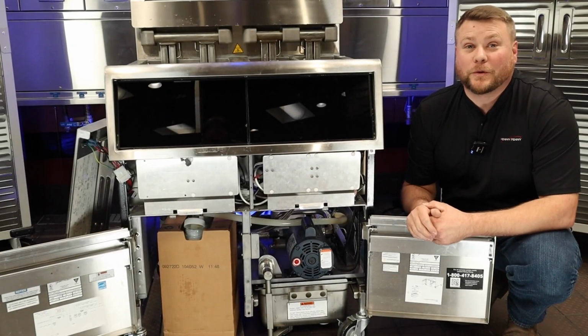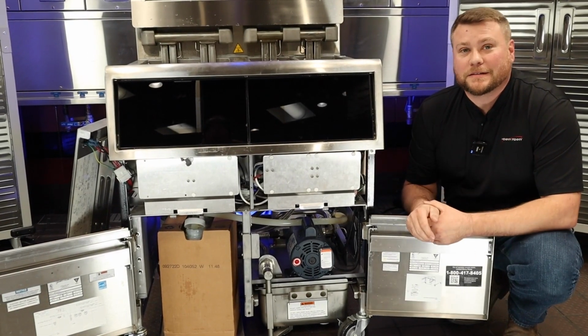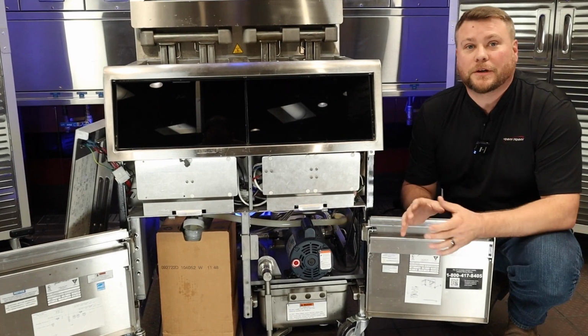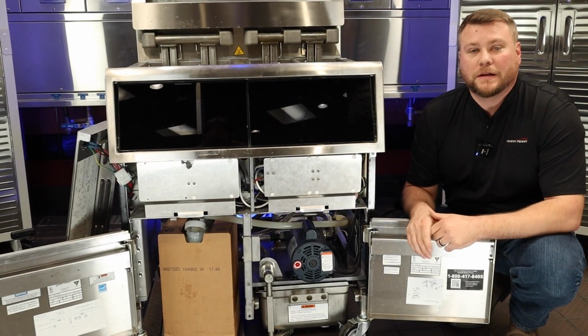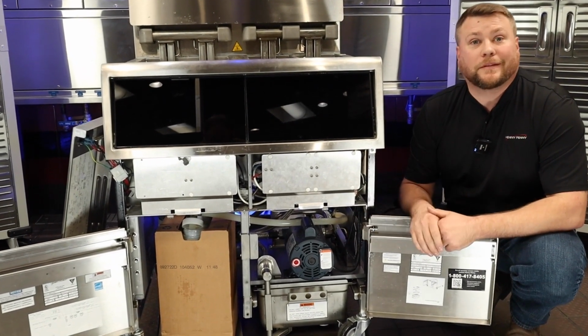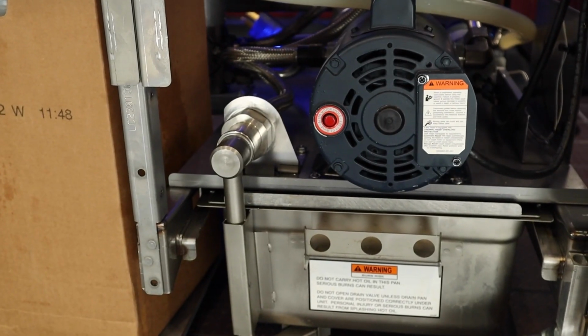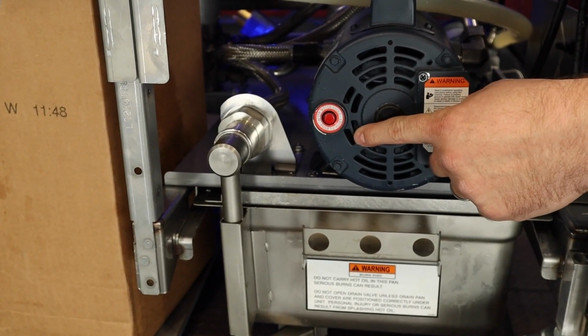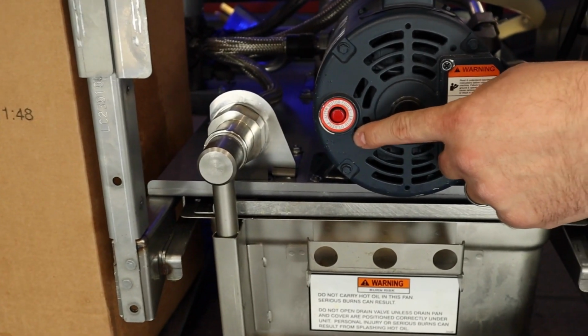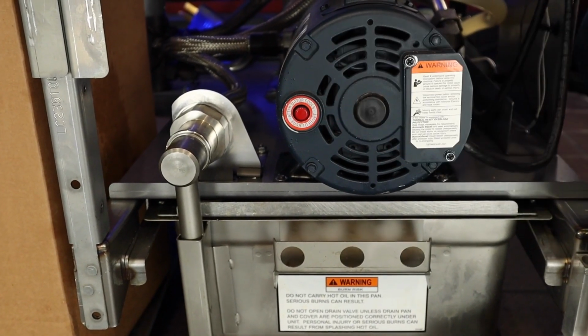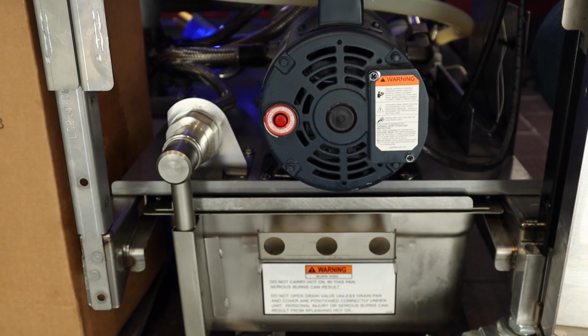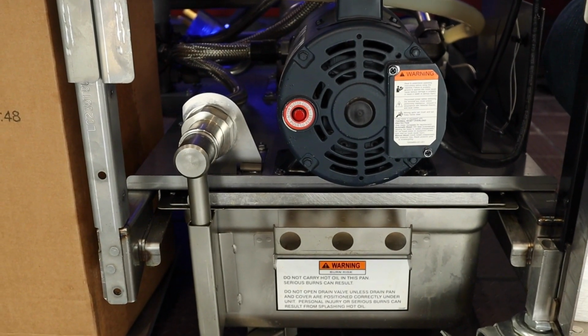All right, enough of the boring technical stuff. Let's talk about the stuff that's going to matter to you when you're in the field troubleshooting and working on these fryers. So let's start with a filter pump motor that won't come on at all. We first need to make sure that the thermal overload on the motor is not tripped by pressing it in and seeing if it clicks. If it does, then we can try energizing it again from the control panel.